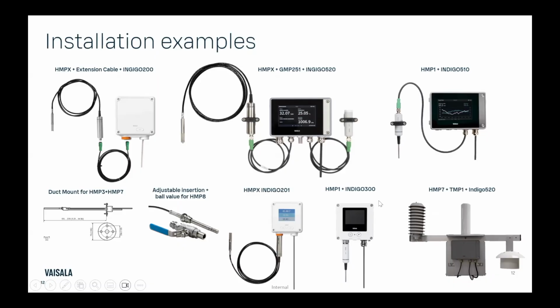And then I wanted to highlight this Indigo 300 with the HMP1. So this is a true wall mount fixed probe design. This is what a lot of people like to see when they see wall mounts. They don't always want something like this Indigo 510 with the cable that's required in between. And then on the bottom left, you'll see our duct mount kit that is compatible with the HMP3 and HMP7. It's designed for that 12 millimeter diameter probe that allows you to penetrate within the duct, run the remote cable down to your transmitter that's wall mounted, and then that ball valve that I mentioned earlier that's compatible with the HMP8 that allows you to hot tap into systems and use that adjustable insertion depth that the HMP8 has to offer.